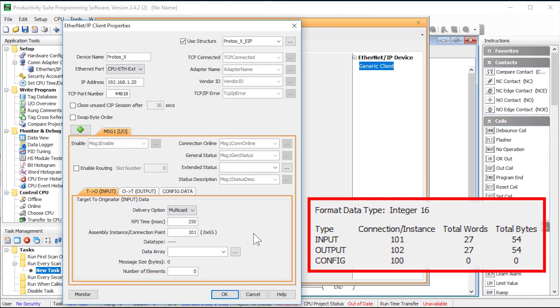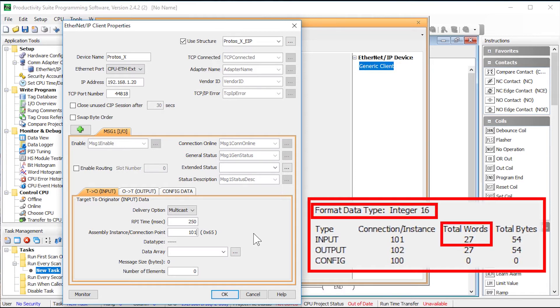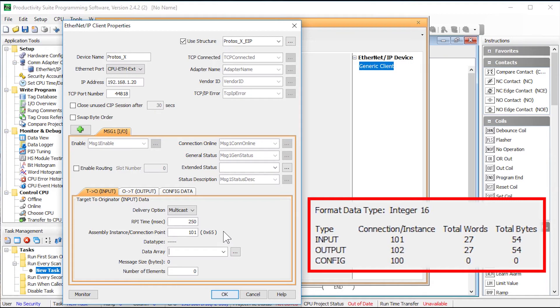The data array data type must match the data size of the input data block. Now from the information that we see here, we see that the data blocks are in 16 bit words and there are 27 of them in total. So we need to create a data array of 16 bit type that has at least 27 columns.